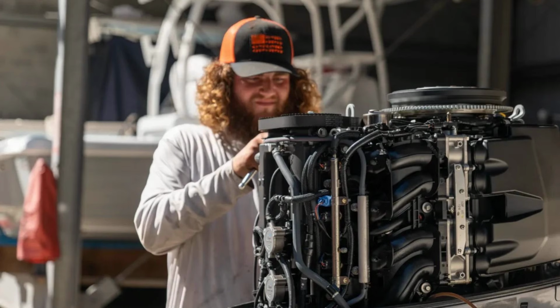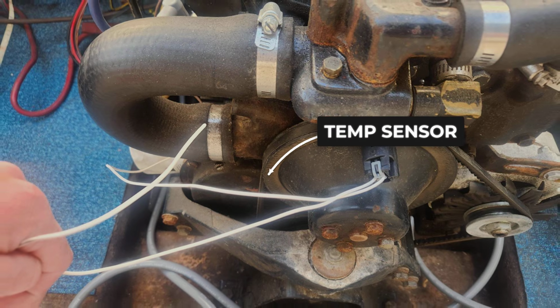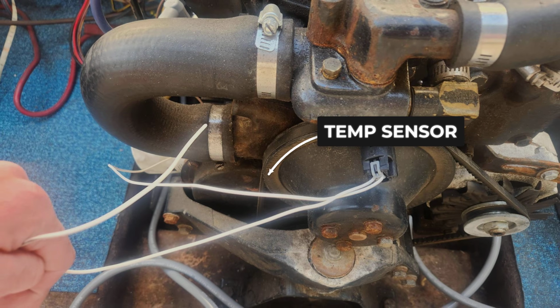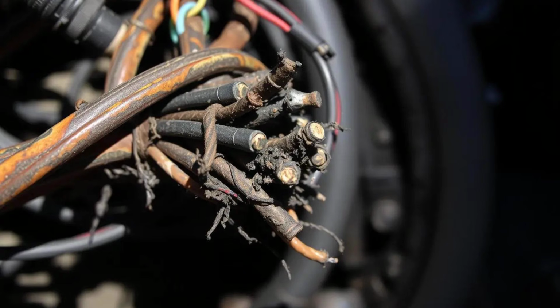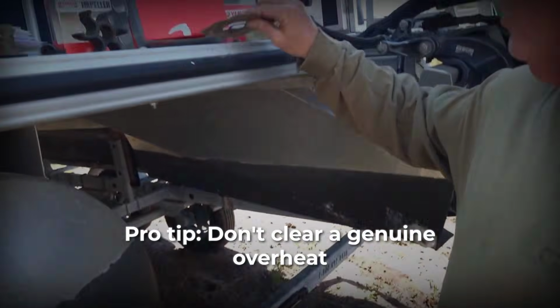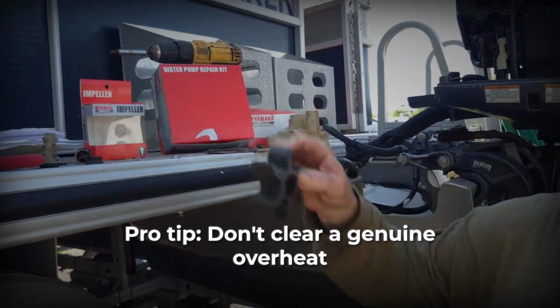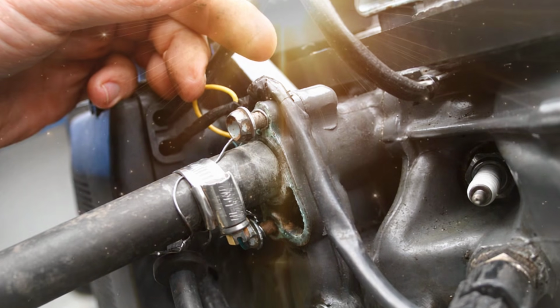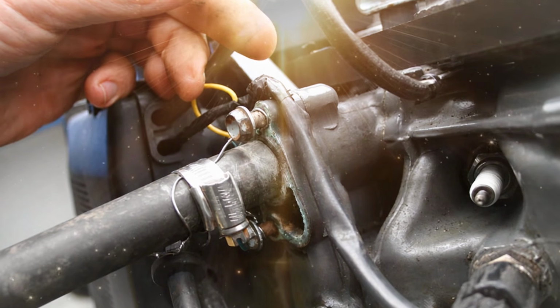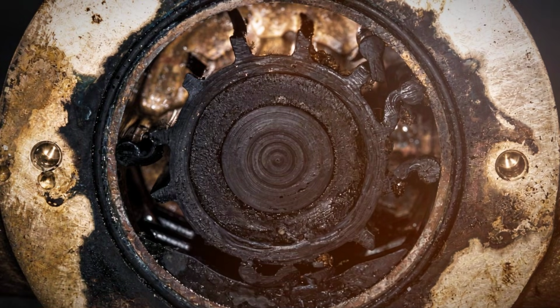Step 4. Inspect and clean the temperature sensor connector. Corrosion there sends false high readings. Pro tip: never reset your way past a real overheat, but a cold motor screaming overheat is almost always a corroded sensor plug or a stuck code, not a blown water pump.